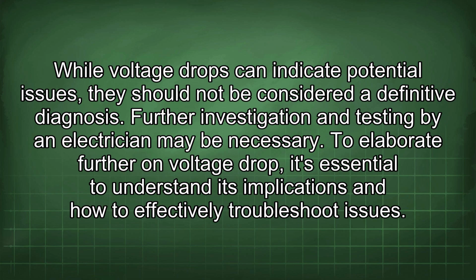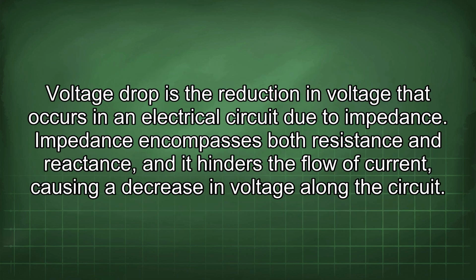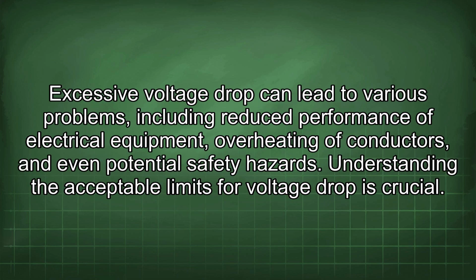To elaborate further on voltage drop, it's essential to understand its implications and how to effectively troubleshoot issues. Voltage drop is the reduction in voltage that occurs in an electrical circuit due to impedance. Impedance encompasses both resistance and reactance, and it hinders the flow of current, causing a decrease in voltage along the circuit. Excessive voltage drop can lead to various problems, including reduced performance of electrical equipment, overheating of conductors, and even potential safety hazards. Understanding the acceptable limits for voltage drop is crucial.